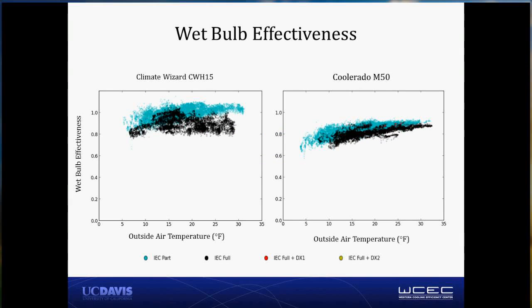Everyone wants to think of performance of evaporative systems based on the wet bulb effectiveness. Some folks call this the saturation effectiveness. It's the nearness to the inlet wet bulb condition that's achieved by the product air or the supply air at the outlet of the system.